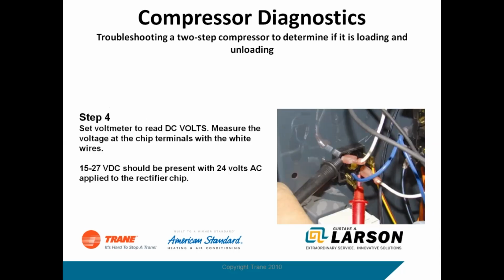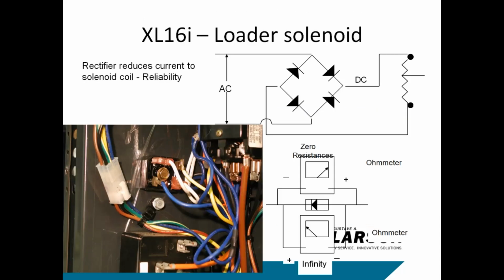And that's basically what it shows here. Look for AC volts feeding the rectifier, and check for DC volts coming out of the rectifier. And here it says 15 to 27 volts should be present somewhere in that area. A little different picture. This just shows the wiring schematic. It's basically a rectifier, and it loads the solenoid in the compressor. Okay, so if you want to ohm this out with an ohm meter, if you get infinity or zero resistance, you've got a bad rectifier.